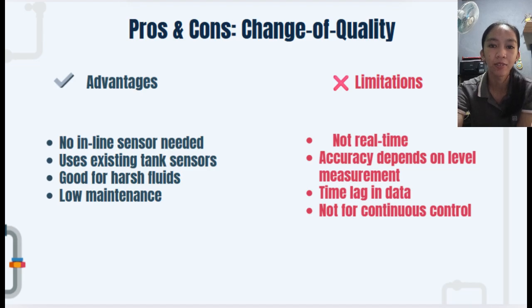Now, let's break down the advantages and limitations. On the pro side, the biggest advantage is that there's nothing inside the pipe to clog, corrode, or cause a pressure drop. You can often use existing equipment like level sensors already on a tank, and it's inherently safe for harsh fluids. While on the con side, the major limitation is that it's not a real-time measurement. You get an average flow over a period of time, not an instantaneous reading. Its accuracy is entirely dependent on how well you can measure the tank level, and because of the time lag, it's not suitable for fast-acting control loops.